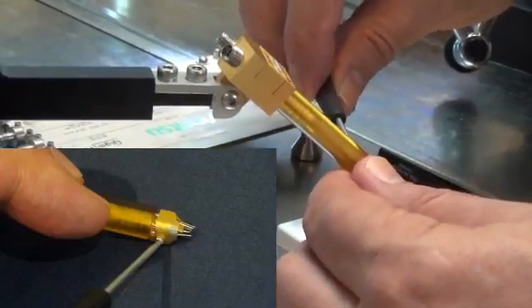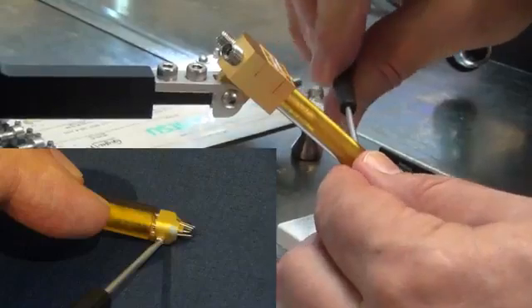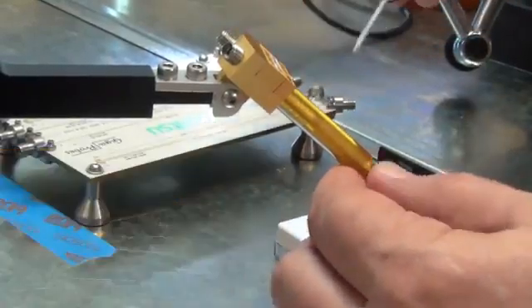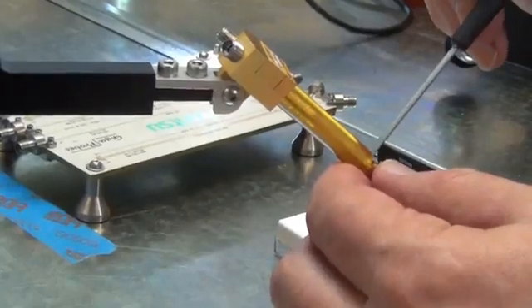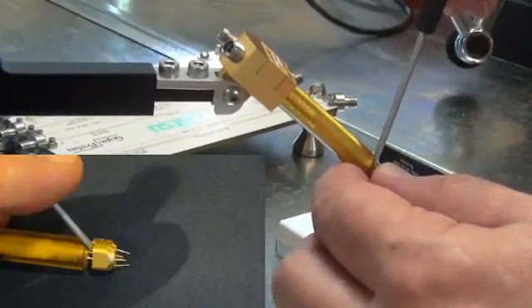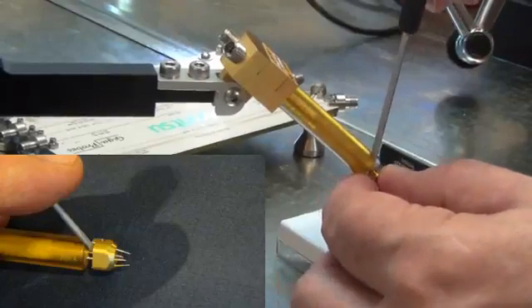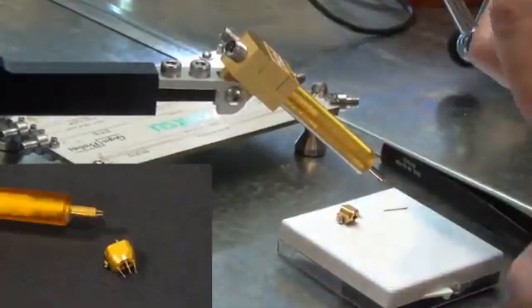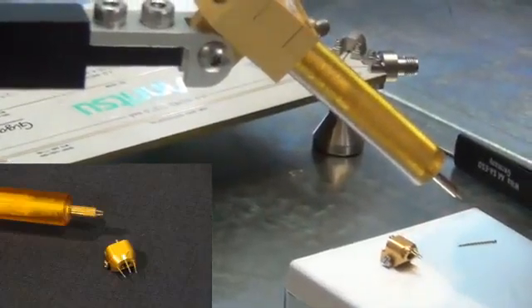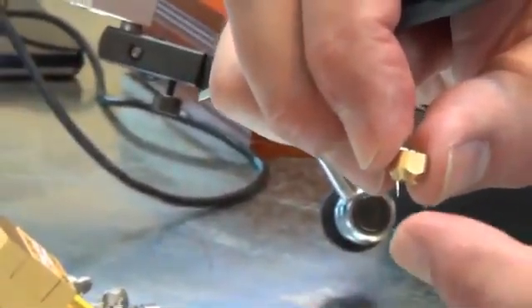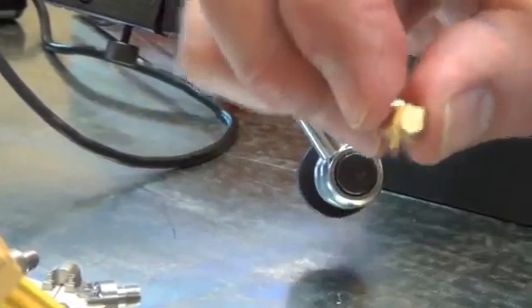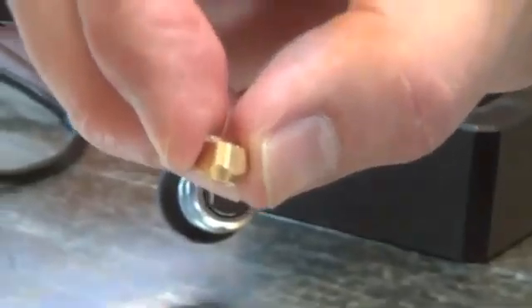So I'm going to hold it with one hand, and this screwdriver comes with the kit. I'm going to loosen the screw, and then put the screwdriver kind of behind it and gently push each side so it slides off, exposing the probe with the two probe tips. And you want to hold it so it's down like this with the probe end down. Otherwise, if I turn it like this too much, the probe will actually slide out and fall on the ground and you'll lose it.